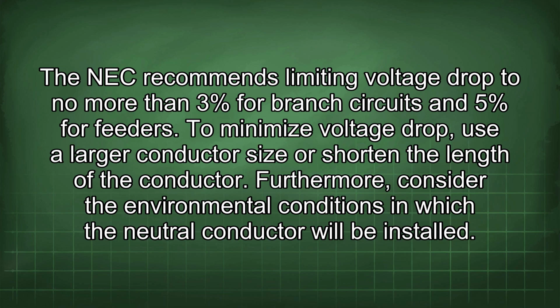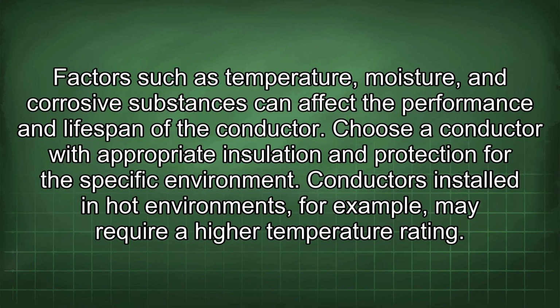Furthermore, consider the environmental conditions in which the neutral conductor will be installed. Factors such as temperature, moisture, and corrosive substances can affect the performance and lifespan of the conductor. Choose a conductor with appropriate insulation and protection for the specific environment. Conductors installed in hot environments, for example, may require a high temperature rating.